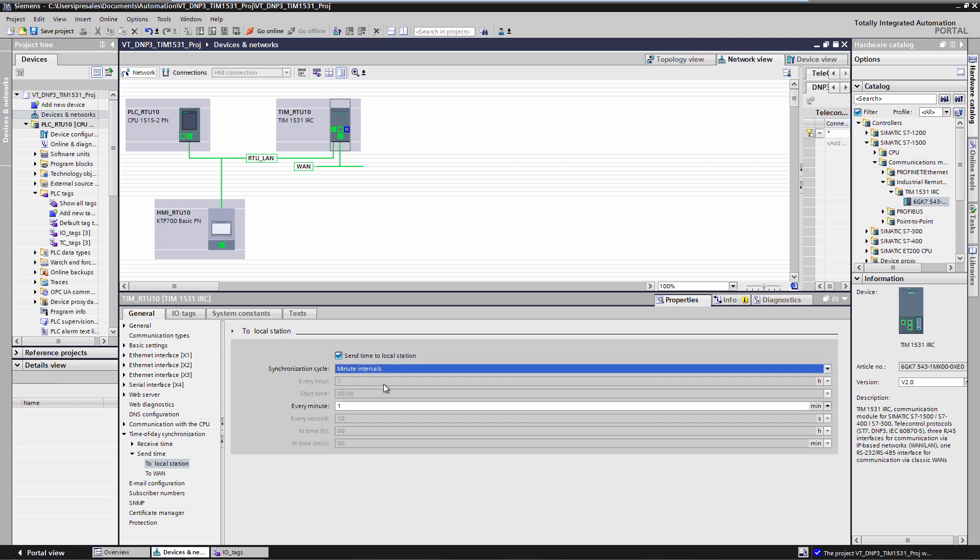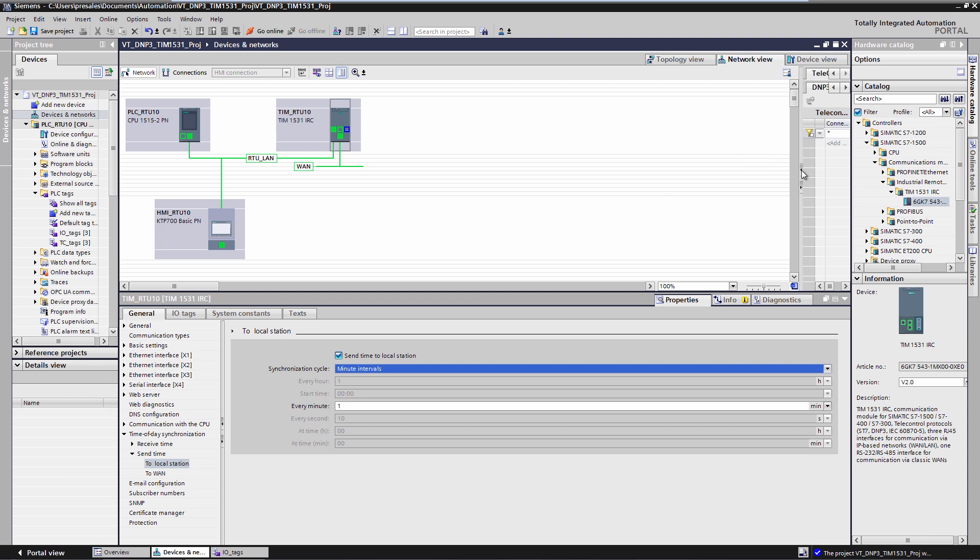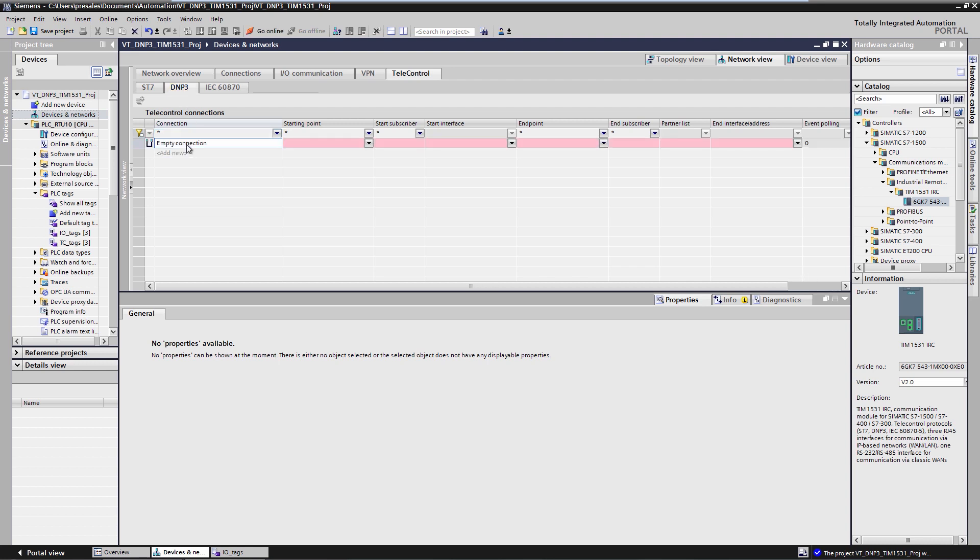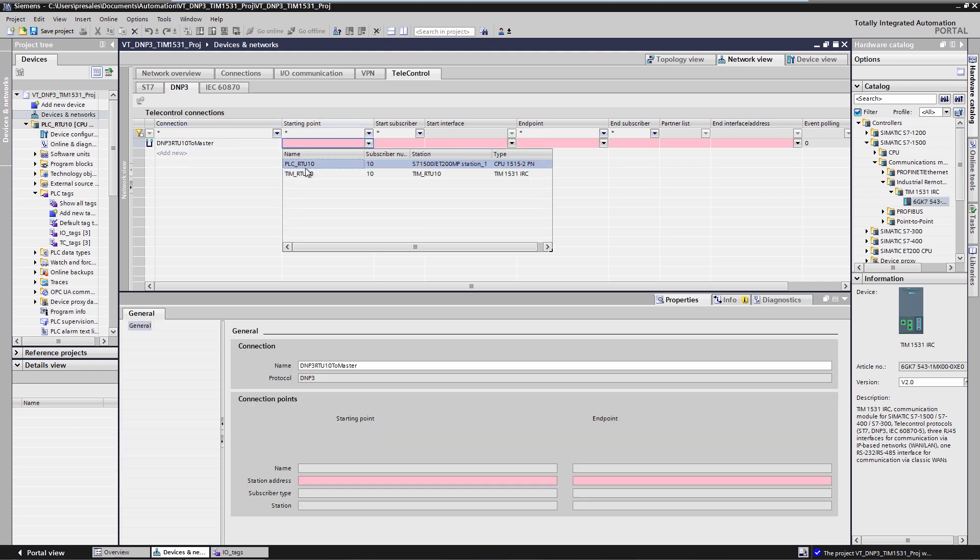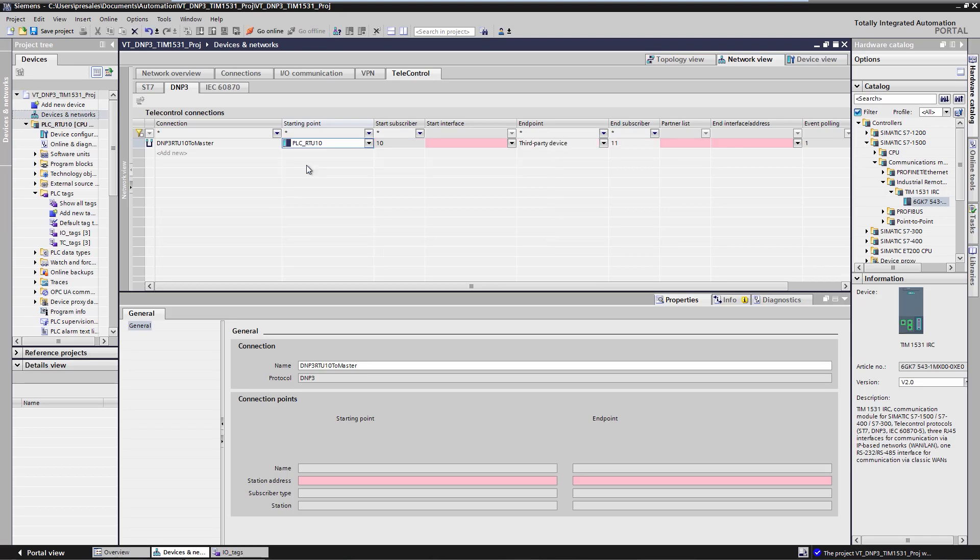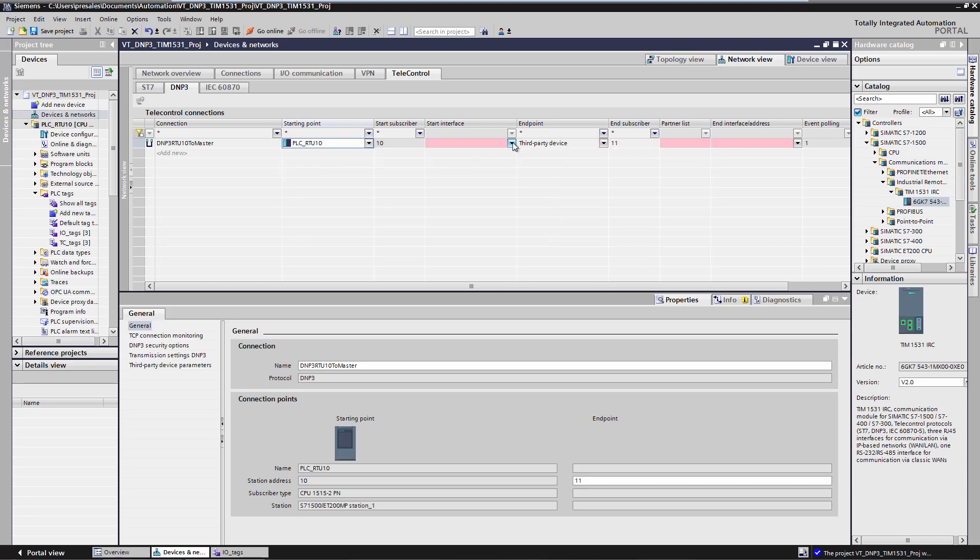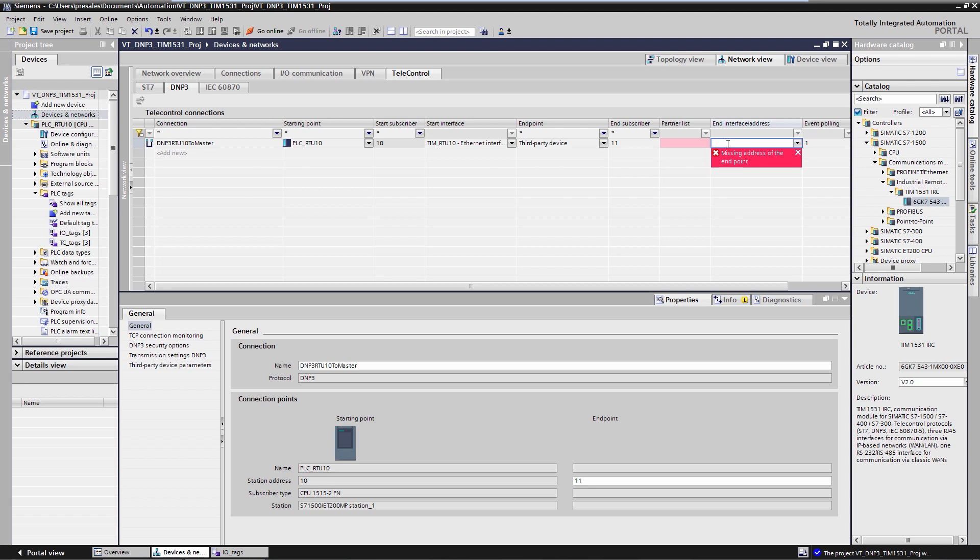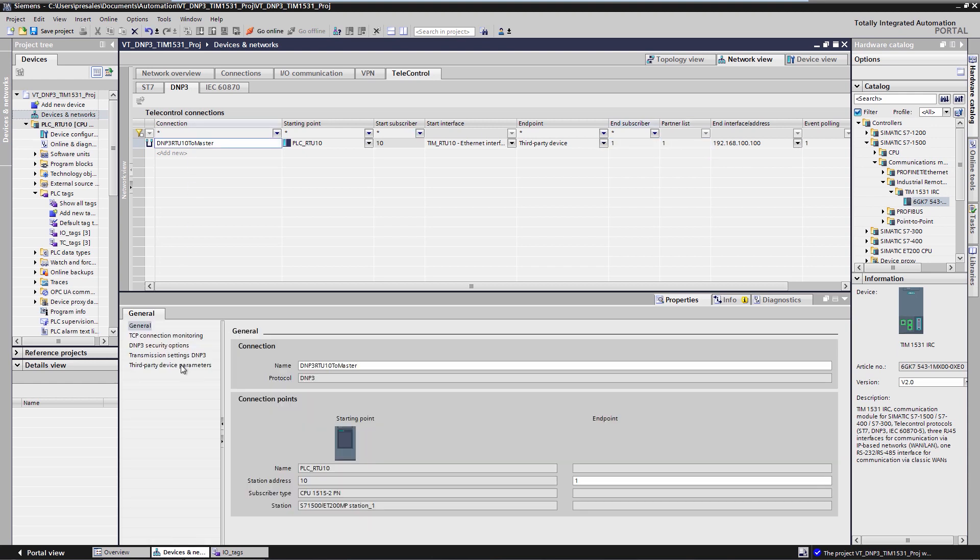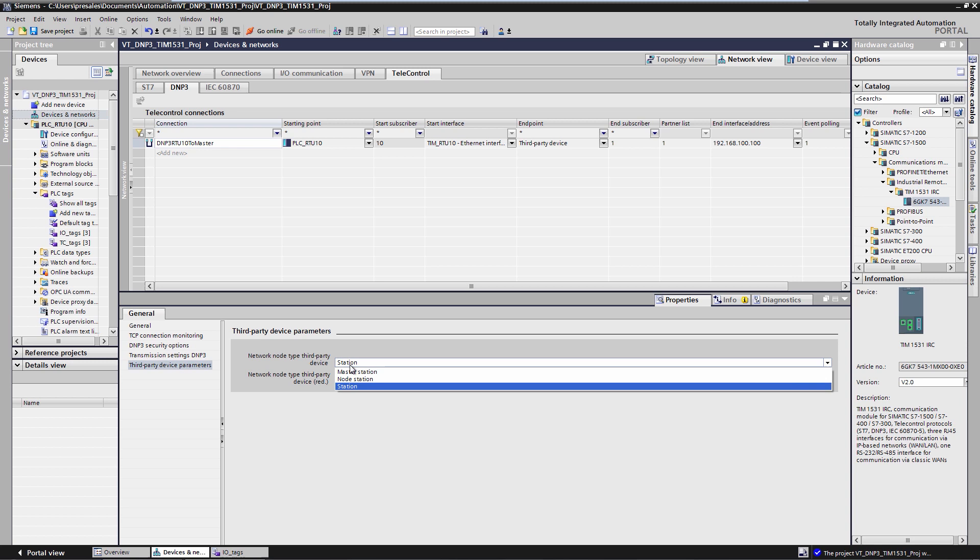Then I configure the connection to the DNP3 master. The RTU must know which DNP3 address and which IP address the master has. Furthermore, we must define via which interface of the TIM our DNP3 master can be reached. For this we change to the connection configuration: Network view, Telecontrol, DNP3. I set up a new connection from our RTU 10 to the master with the DNP3 address 1. The starting point is RTU 10, connection via TIM X1 interface. Master or endpoint is DNP3 address 1 with IP address 192.168.100.100. The DNP3 partner is of the type master station.